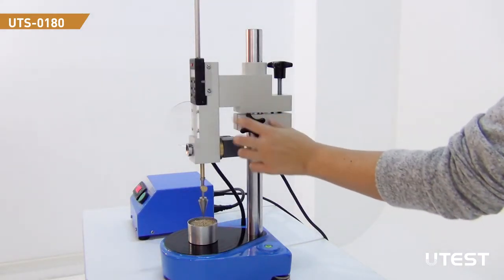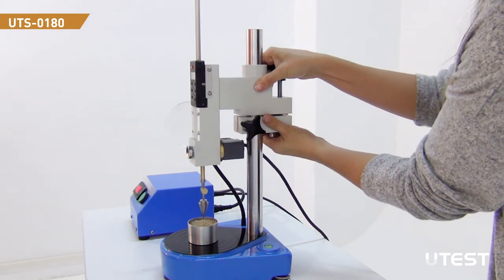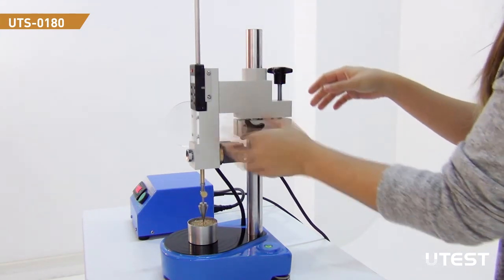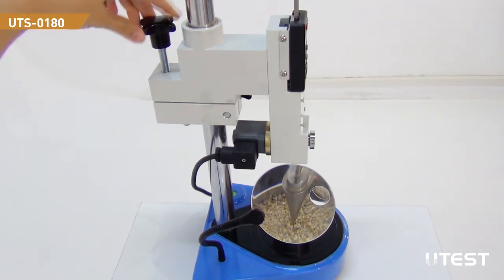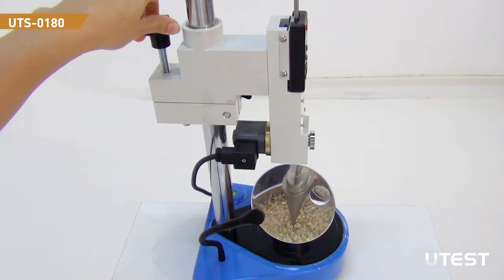Use the fixing nut to move the holder and adjust the cone. For fine adjustment, use the second nut — turn it right or left to adjust the cone just to touch the sample.